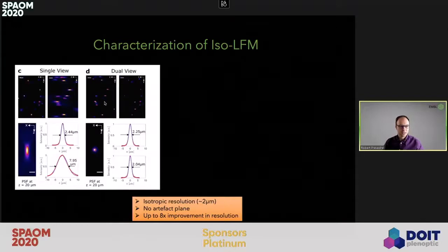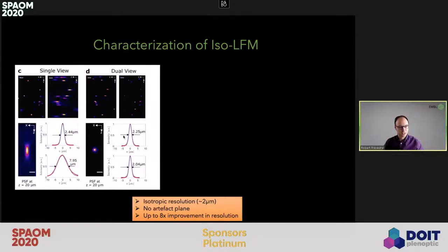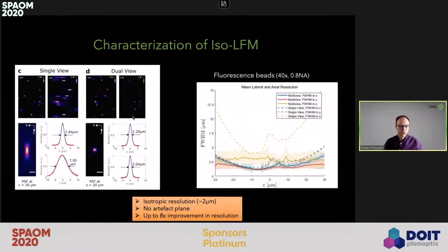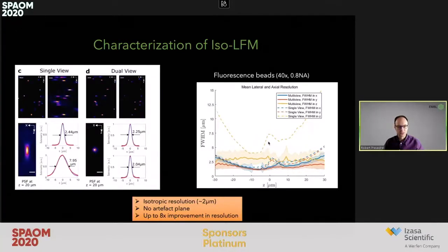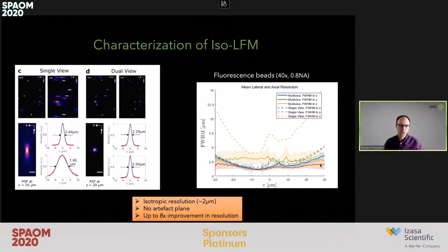Comparing a single objective light field — a typical epifluorescence light field microscope — to the same beads imaged with our dual-view ISO-LFM approach, there is no real difference in the lateral resolution, but the axial resolution is dramatically improved by a factor of four, really reaching the isotropic regime. Even more importantly, we avoid the typical problem where axial resolution gets much worse with increasing imaging depth. In our dual-view approach, we have an almost constant and isotropic resolution throughout the imaging volume, and there is no artifact plane.